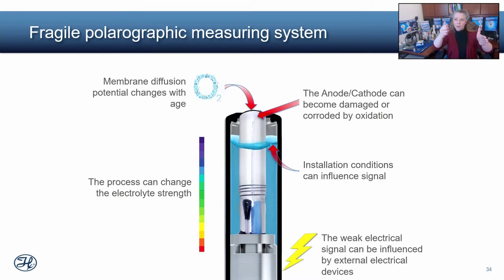Your bioreactor's here and your controller's here. And between those two, maybe you have an oven. Maybe you have a couple pumps that are feeding in acid or base to your bioreactor to maintain a stable pH. Maybe they're pumping in food because you're feeding glucose to your cell culture. That pump has a vibration. The cable is running right next to the pump, which is vibrating, which is kind of like a series of tiny little flicks. So the environment that you're in can influence the signal read, not the actual measurement, but the reliability of the signal. Nanoamp is very weak. This is not necessarily valid on short cables, but anything over about 10 meters has a significant impact. Okay, so you need short cables for this to be reliable.